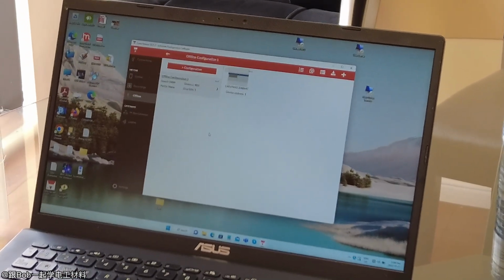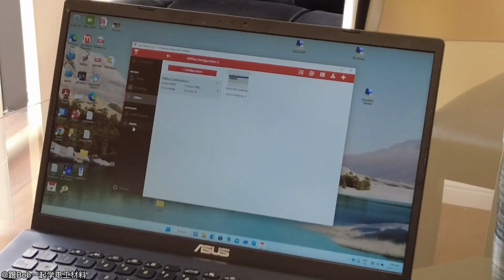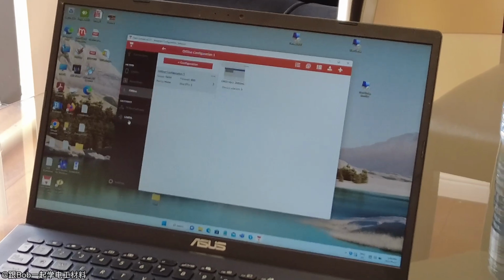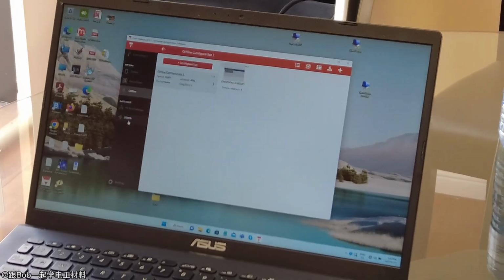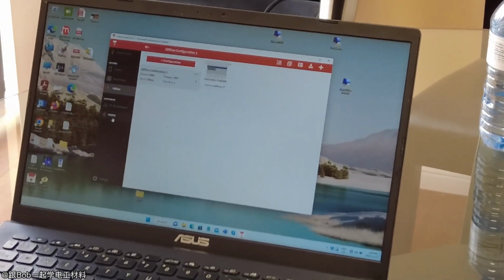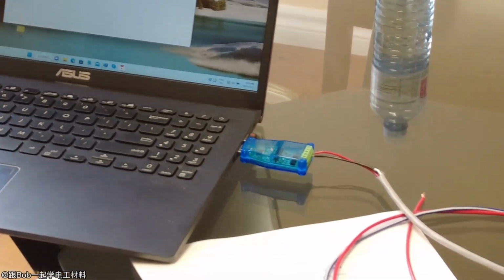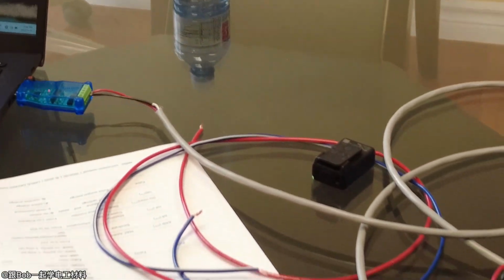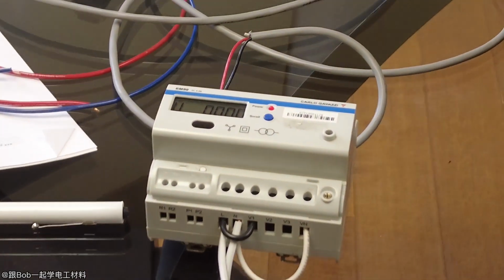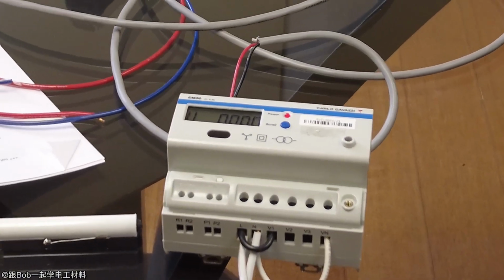If you have anything that requires wireless, we have a system here that uses the UWP, and it's a little module that we hook into this one. What it does is it uses a wireless communication called LoRa, however you want to pronounce it. With line of sight between this and ours, it can be like 1 kilometer, quite long distance. And if it's for a building, it has quite good penetration through walls. So we have one in our office, and then we have 3 units in the back that we're monitoring wirelessly like that. The other option is if somebody already has their own LoRa network.